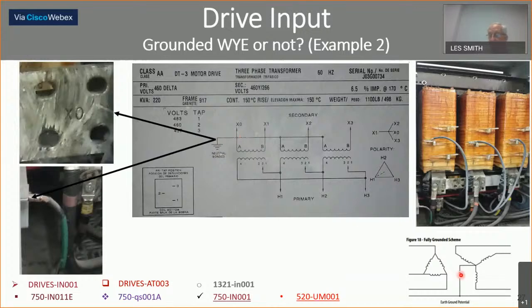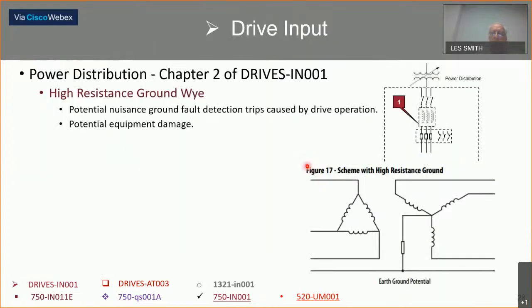And again, I asked, and we finally took the cover off of this big bad boy. This was 300 horsepower, so it's probably 250 kVA. And we saw this. And this one, we had all the jumpers come out. We deemed it ungrounded. And this is a high resistance ground. We put a resistor in the ground here. Either leg, any leg can go to ground and will continue to run.